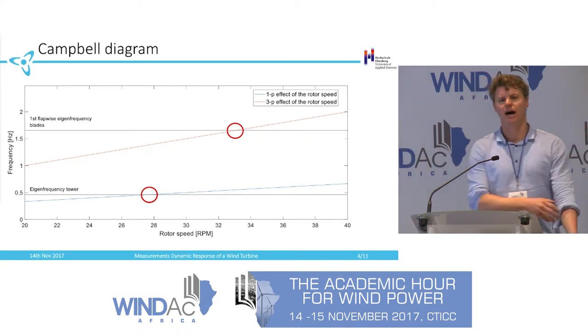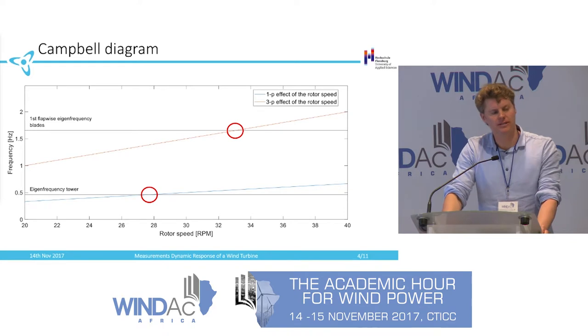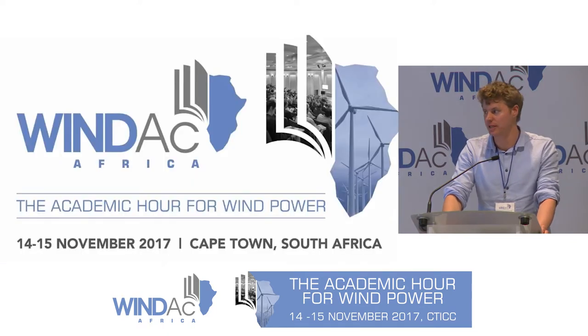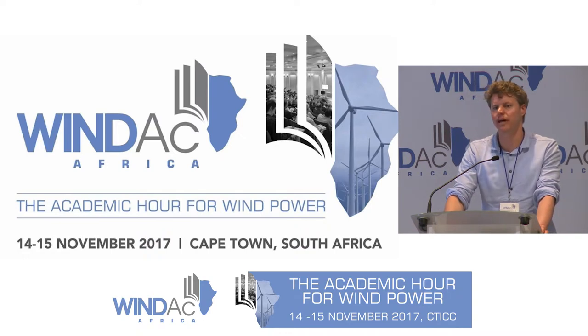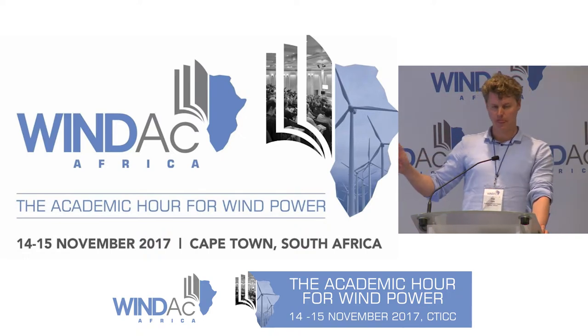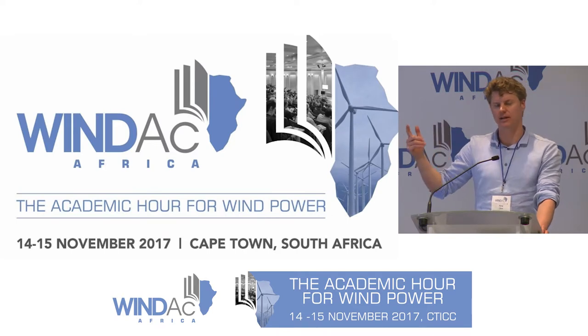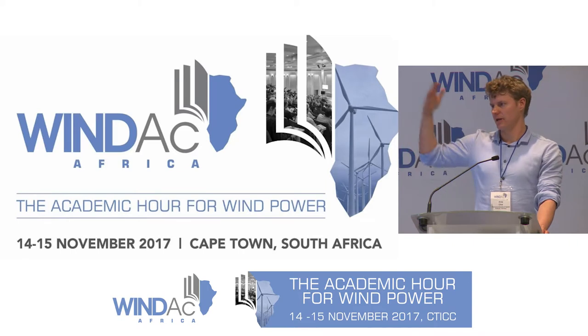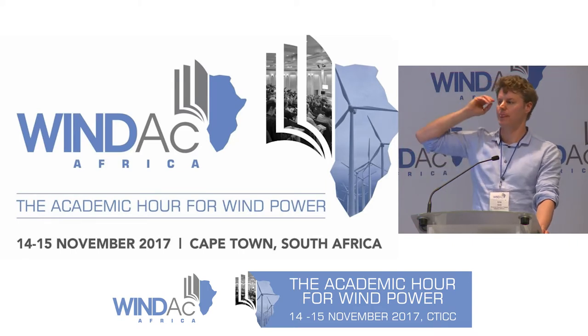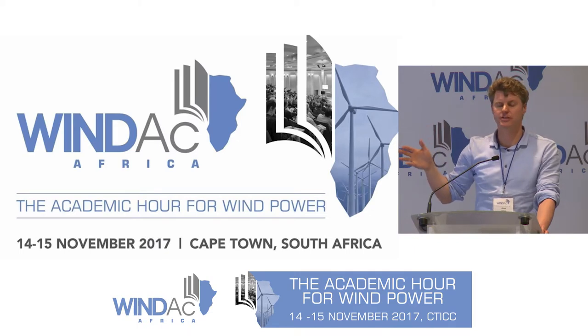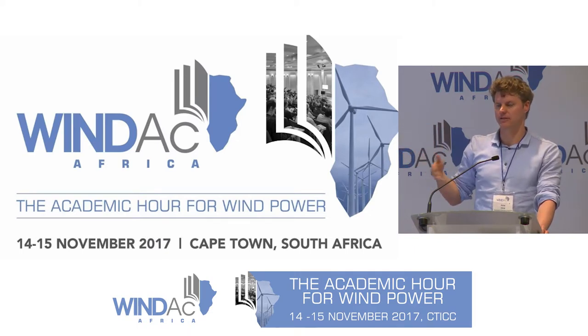The second one is how do these mechanical vibrations affect our power production? And for that we did what is called an analysis of frequency spectra. So we basically compared the frequency spectra of the rotor speed with the one from the DC link and the one from the grid power and looked at whether the peaks in the spectra are at the same frequency. So as I said before, we analyzed basically two situations. One was where we are in resonance, so that the rotational speed is at the eigenfrequency of the tower.